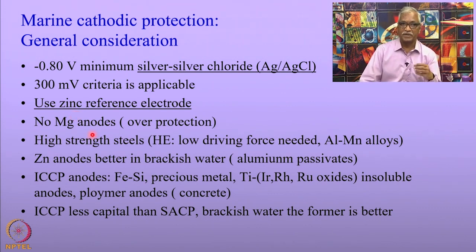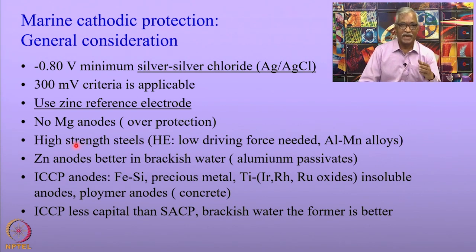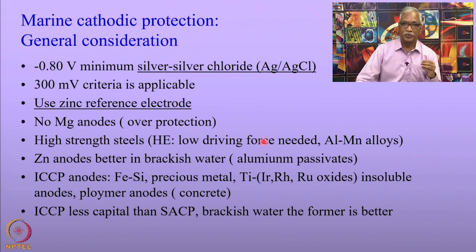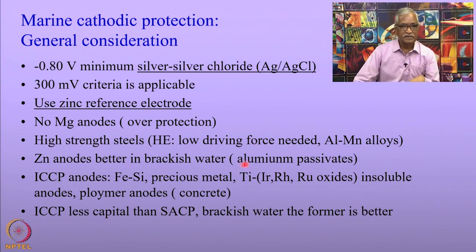No magnesium anodes are used in marine applications because they will over-protect the structures. Where high-strength steels are used in marine applications, since they are prone to hydrogen embrittlement, low driving force sacrificial anodes are required. One such anode is the aluminum-manganese anode.